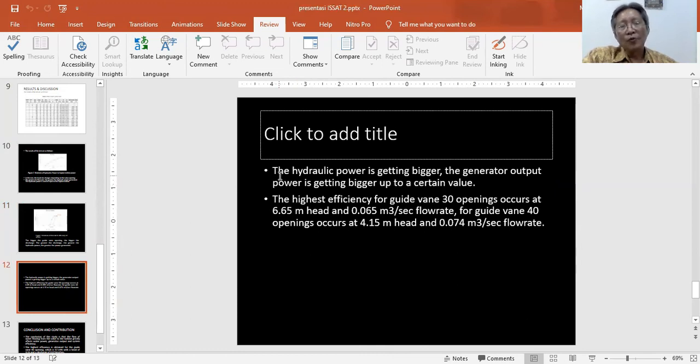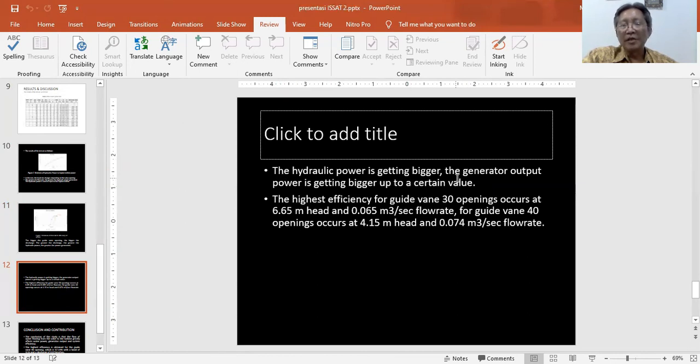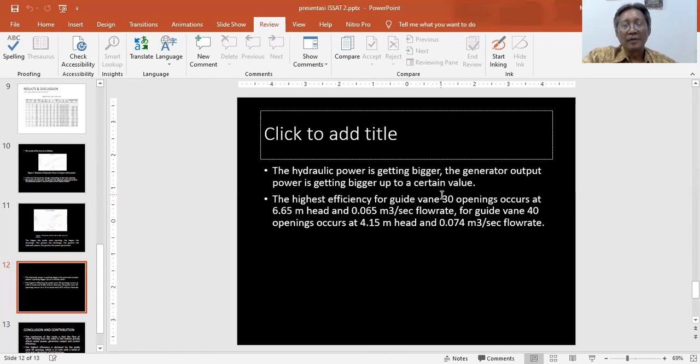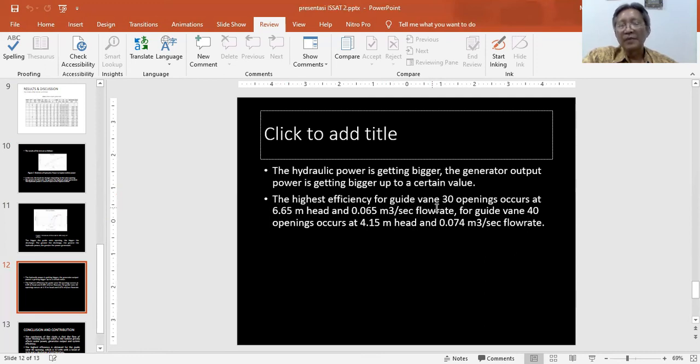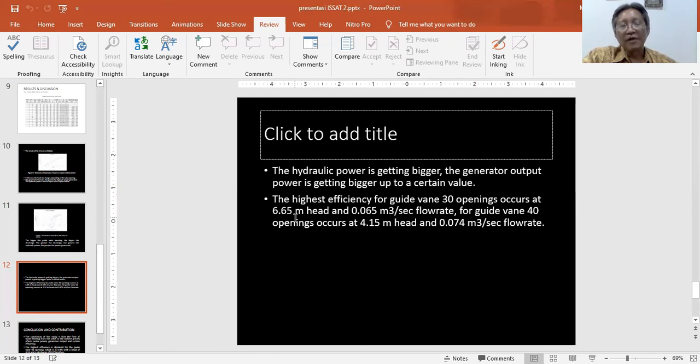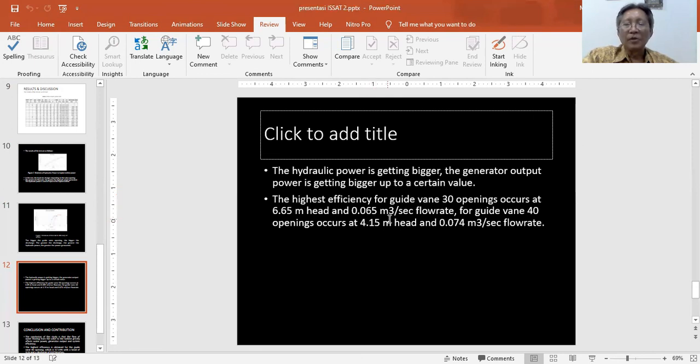Also from the figure, we can conclude the hydraulic power is getting bigger, the generator output power is getting bigger up to a certain value. For the figure, we can conclude the highest efficiency for gate vane 30 degree opening, occurring at 6.65 meters head and 0.065 cubic meters per second flow.